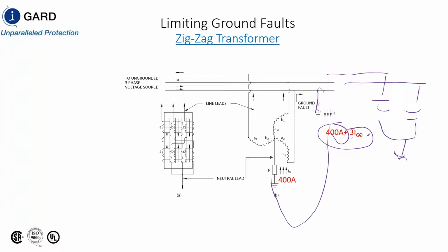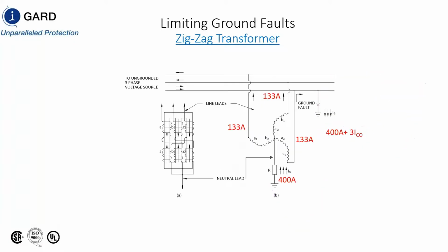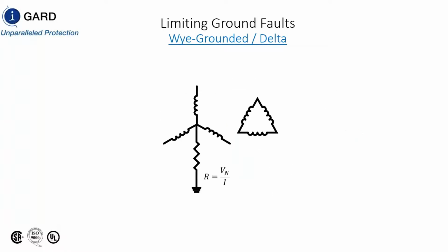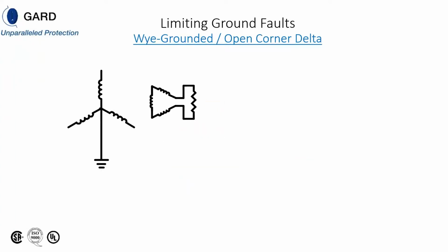So if it's a 13.8 kV system, you have 20 ohms. You have 133 amps returning on each phase because all three phases contribute to that fault. And you have a 960 kVA transformer if it was rated continuously. If it's rated for 10 seconds, you're allowed to derate that transformer, and the typical derating is about 3%. A Y-grounded delta transformer still has the same 20 ohm resistor over here. You still have the 400 amps, 10 seconds, and 133 amps per phase. Now you still have 960 kVA in that fault, and it can derate to 10 seconds.